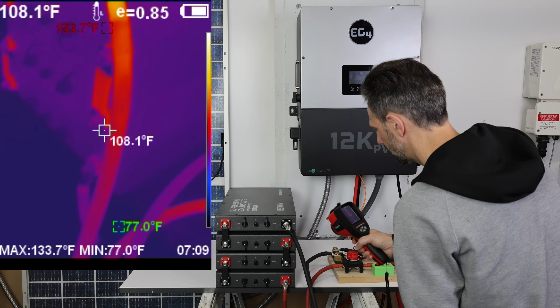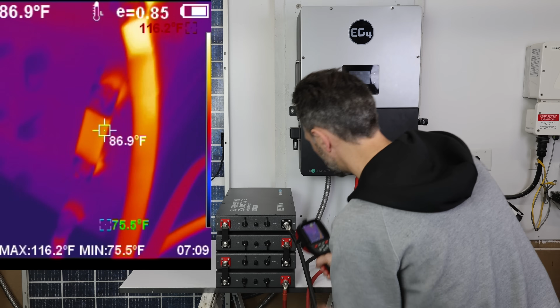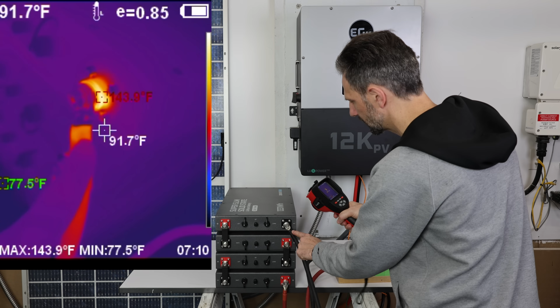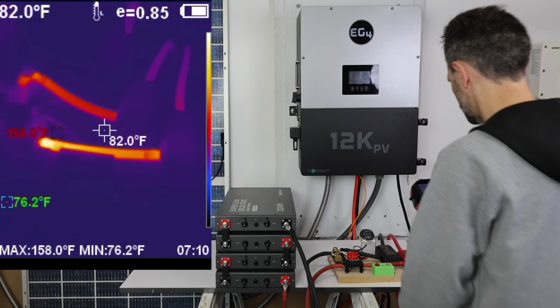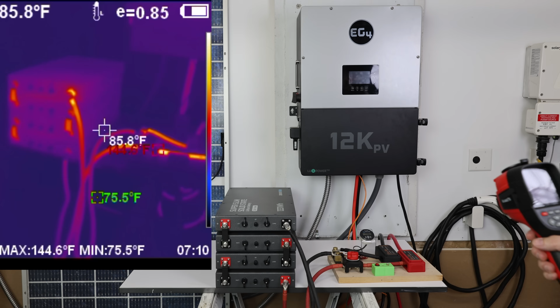The cables themselves are just barely warm, a little over 100 degrees. This post is way warmer, which tells me maybe that one has insufficient torque — something going on there. Could be that this isn't clamped properly. This is a 1-aught cable, and you can see how much significantly warmer that one is. That's a great way to check on your system.